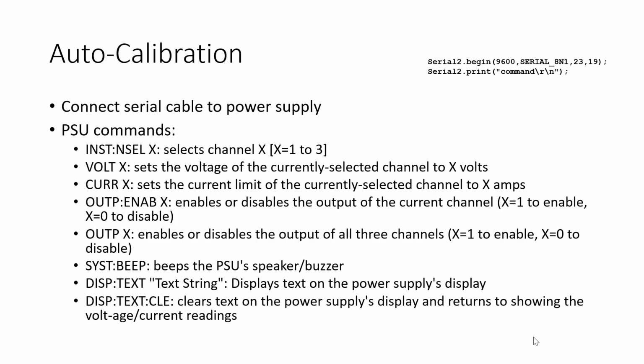And you have to hit the on off button in order to actually see what they're set to. Yeah, that's what I was saying before. This one's set to 18 volts on channel 2. Zero all those out just to be safe. If anyone needs help zeroing them out, I can help with that.